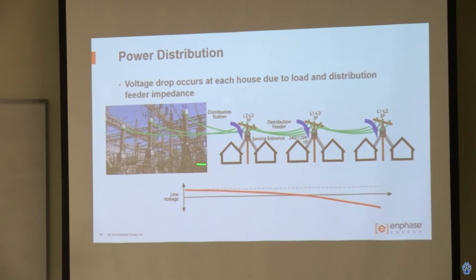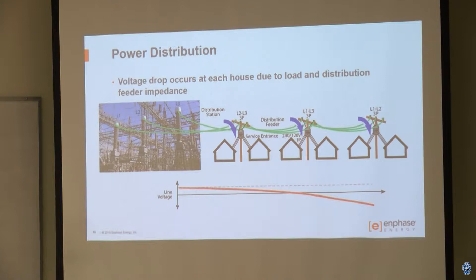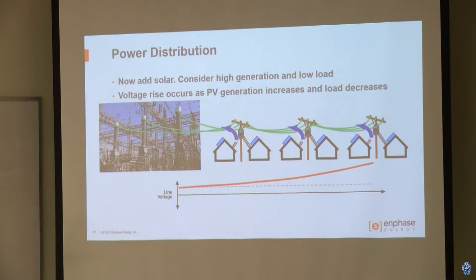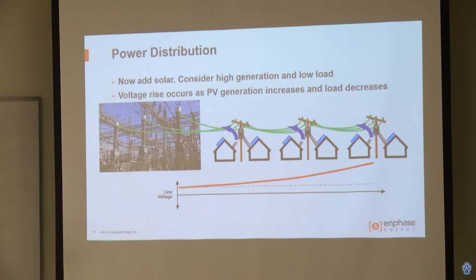Now, let's say we add solar to the whole thing. Solar is generating energy, and it's at its peak during the day when the sun is out — but most of us are at work, so the load is low. Eventually you start feeding current backwards, and what that does is raise the voltage at the end of the feeder. You have wide extremes between the fully loaded case and the fully generating case. Voltage rise occurs as PV generation increases and load decreases.